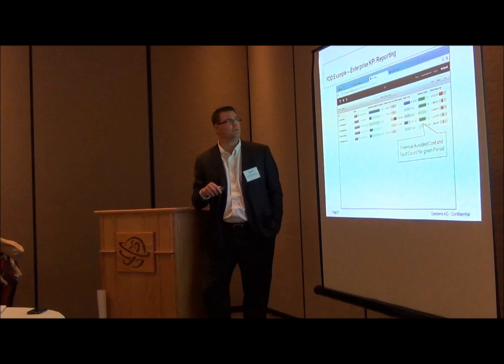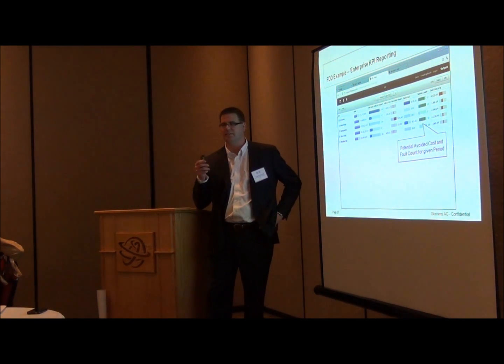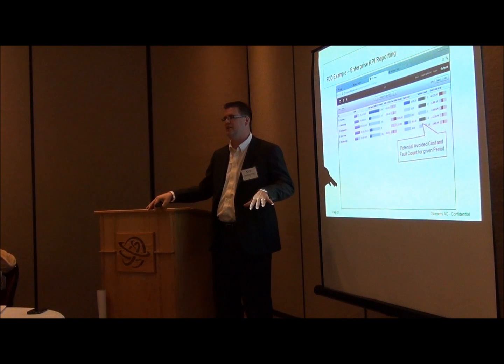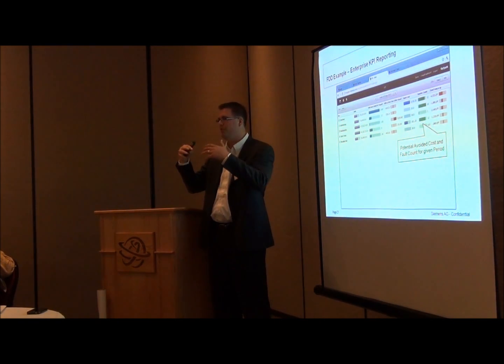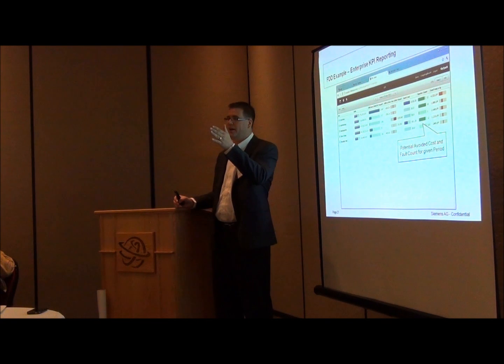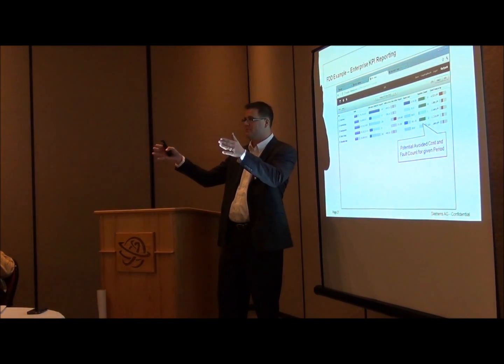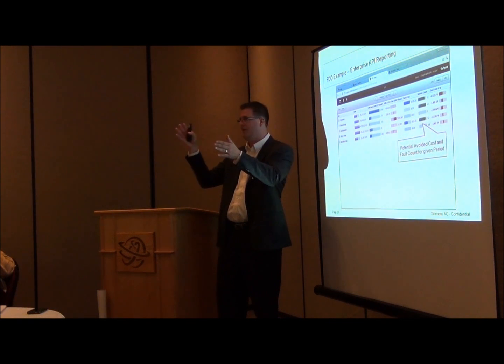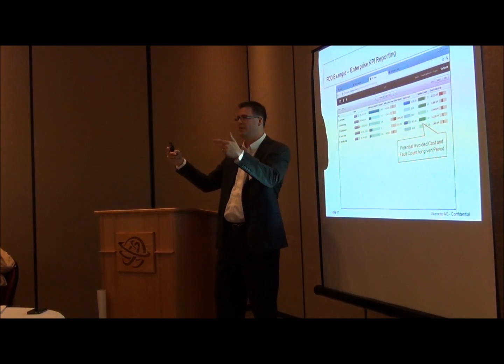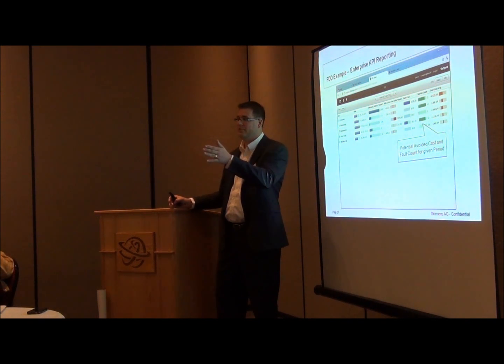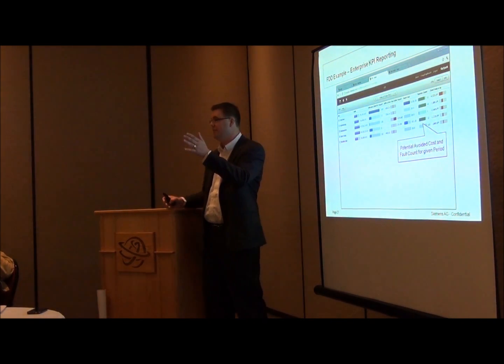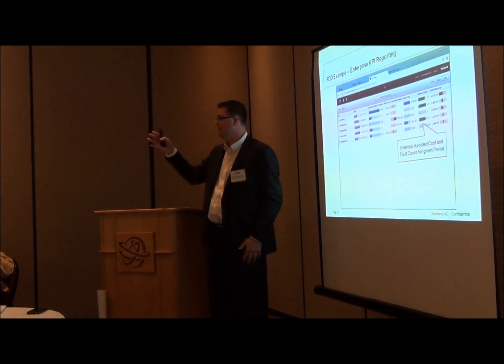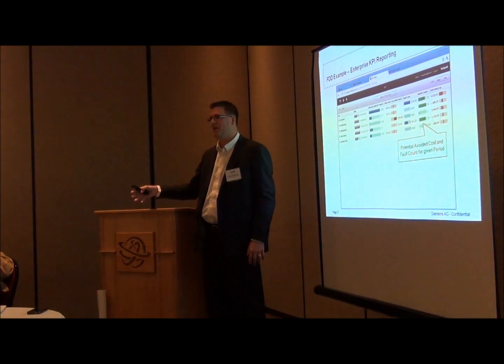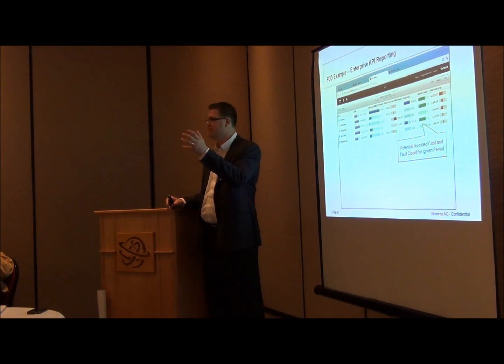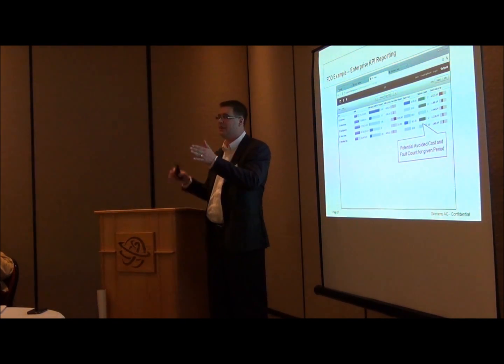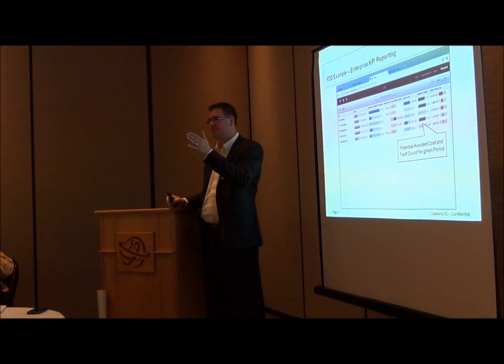Here's some other examples of actionable information: fault detection diagnostics. Simple concept - you take all this data, mine it, run algorithms, and find things like simultaneous heating and cooling, where the cooling valve and heating valve are both open when they shouldn't be. The first step is identifying that. The second step is the diagnostic showing five possible causes - maybe a valve is leaking. The next step is pinpointing it further - it's valve number 7, and you need to go fix it.